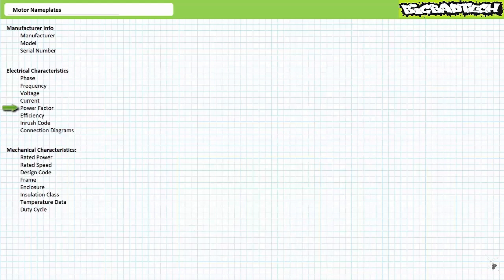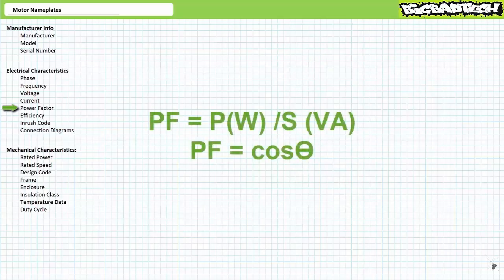The power factor entry on a motor nameplate is a measurement of how much apparent power, in units of volt amperes, being delivered to the motor is available for conversion into real output power in units of watts. Power factor is several things: 1, the ratio of real power over apparent power, or 2, the cosine of the phase shift between voltage and current. Motors are inductive loads and current will understandably lag voltage.